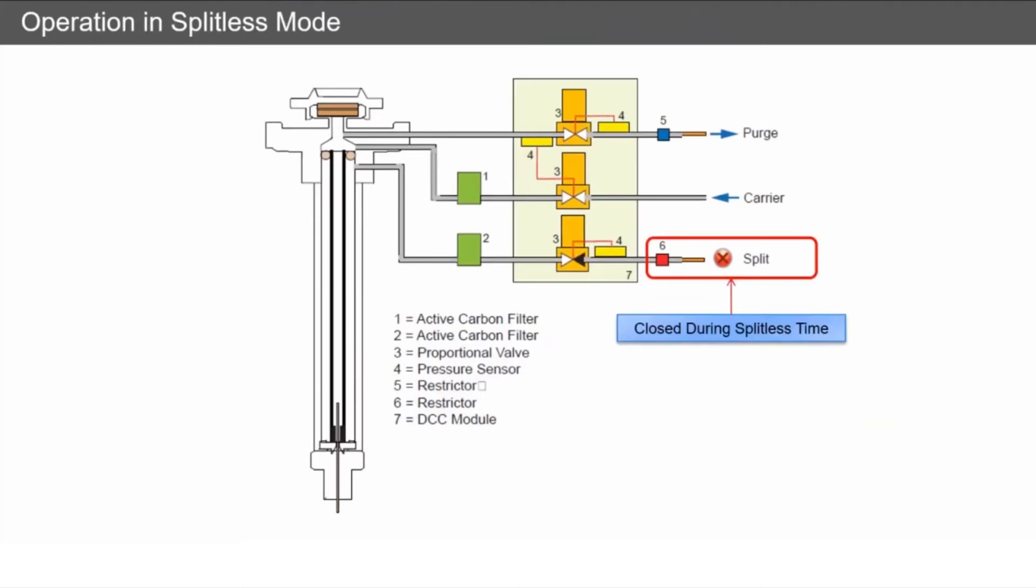In splitless mode, we want everything that we inject to go onto our column. While the injection happens, we've got a flow coming in for our carrier and a small flow coming out the purge. But as the injection takes place the split valve is closed, which means that everything from the carrier and your injection is passing onto your separation column.